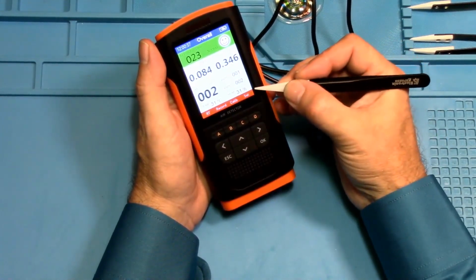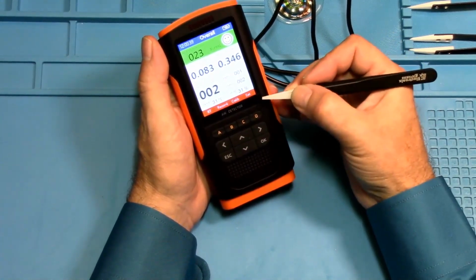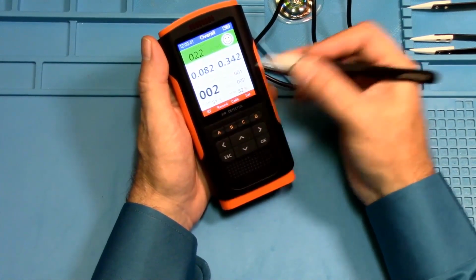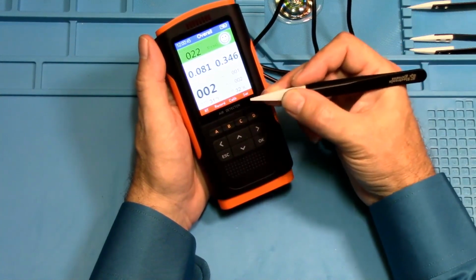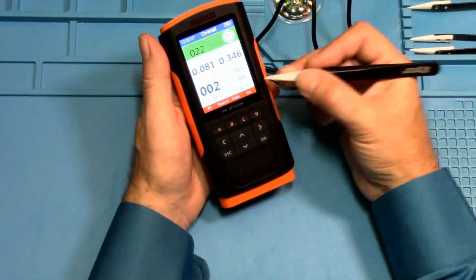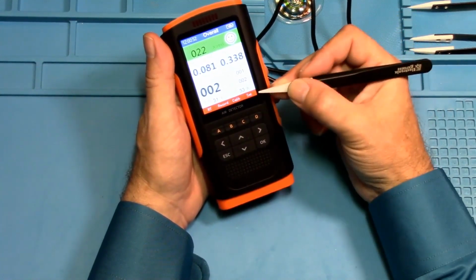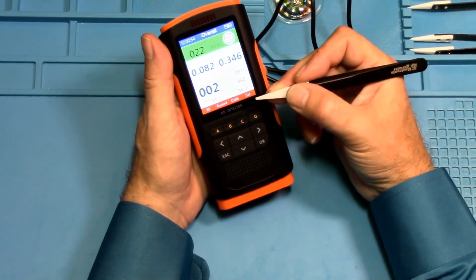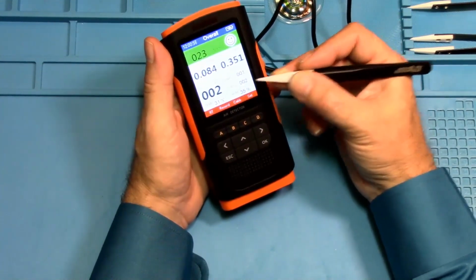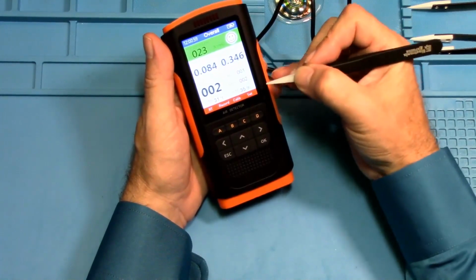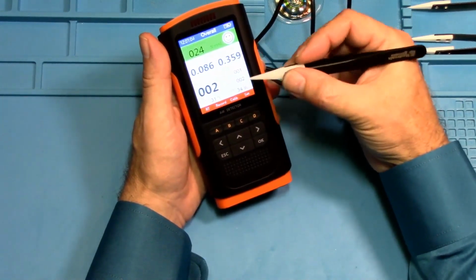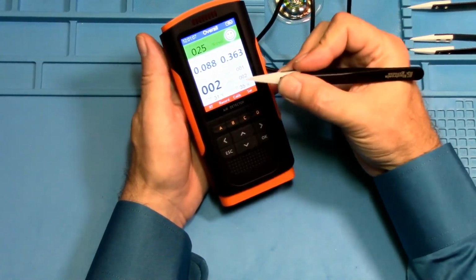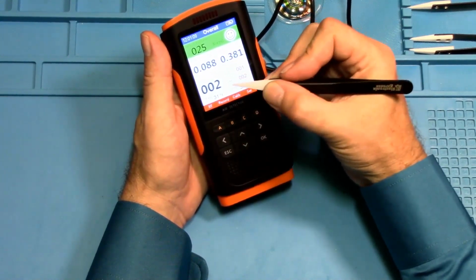And then remember, if you're in this screen, the A button will be for calibrating the device. So when you first get this, take it outside or in fresh air, and just leave it set there out of the box. I had mine on, so you can turn it on, plug it into a power source, and just let it sit there for 3, 4, 5 hours if you want, or all day. The longer the better that you leave it in fresh air initially. That's what I call a manual calibration. And then after that, do the calibration per the manufacturer.